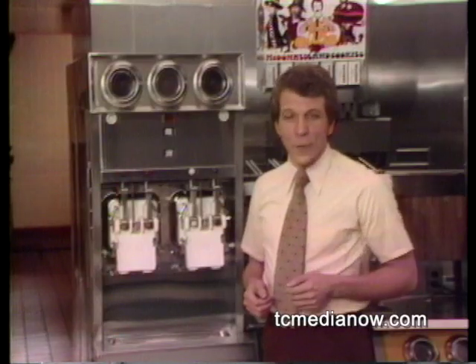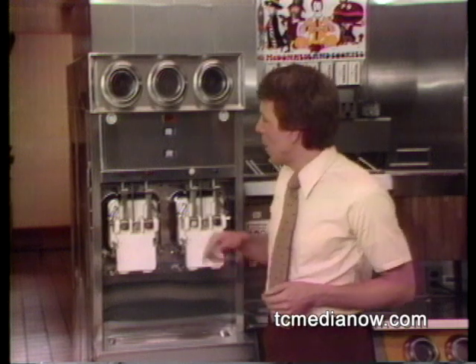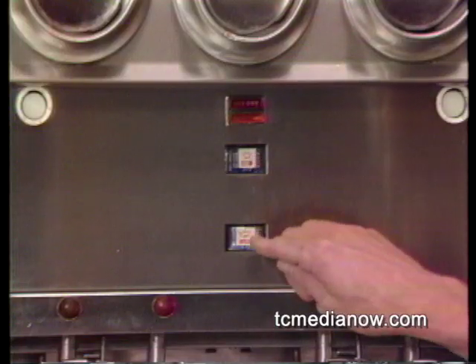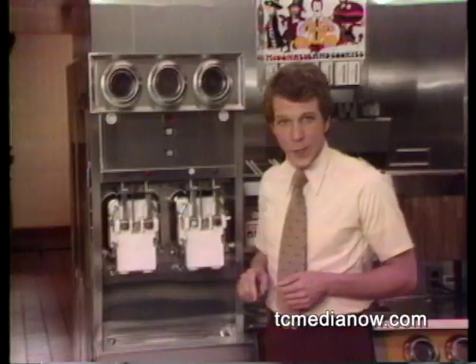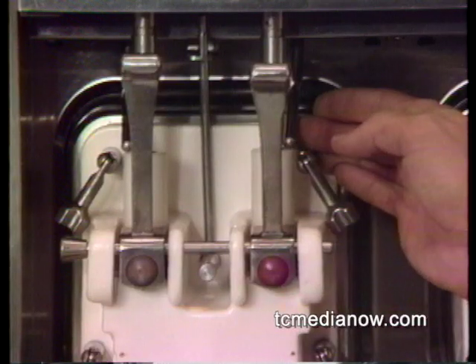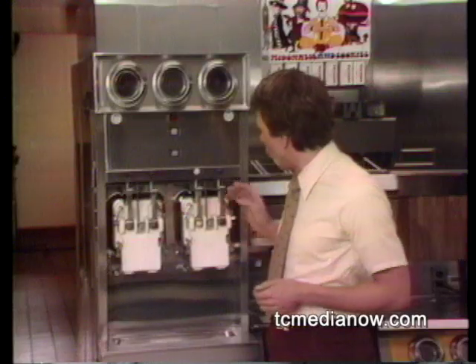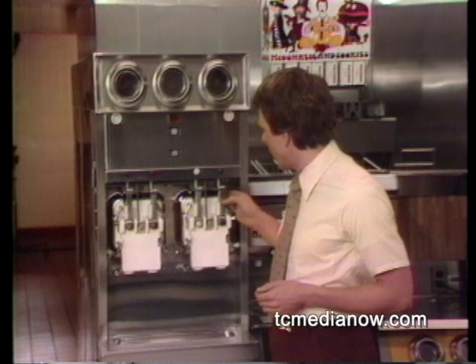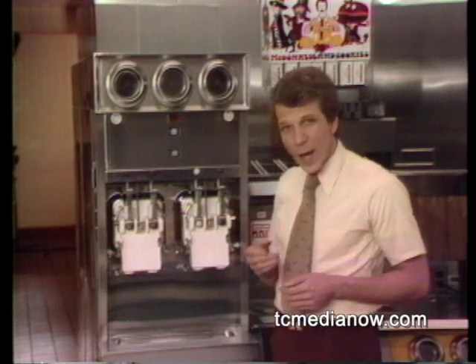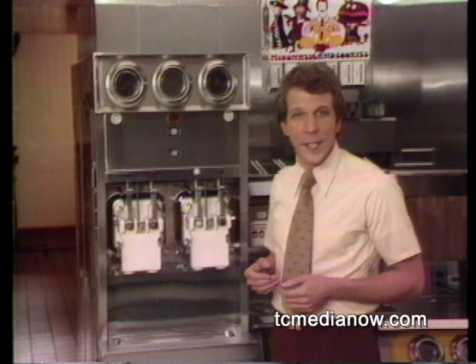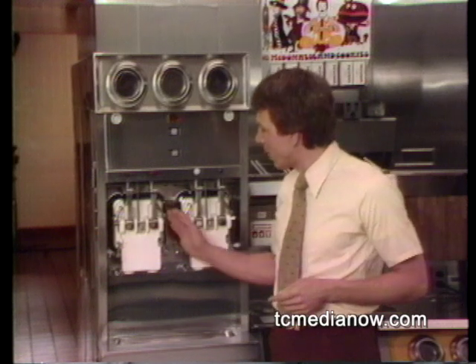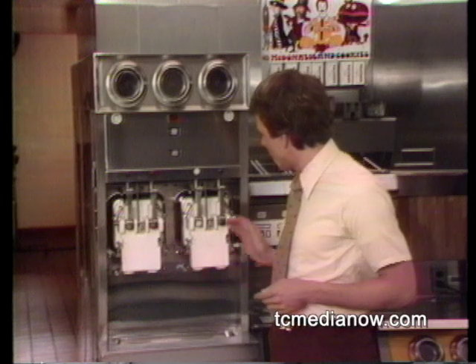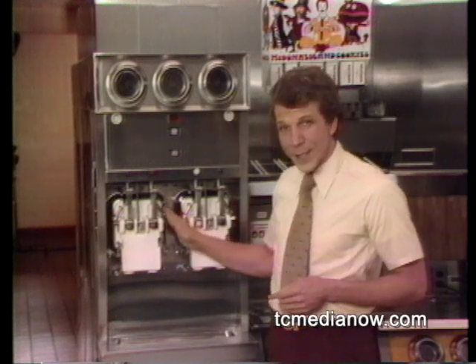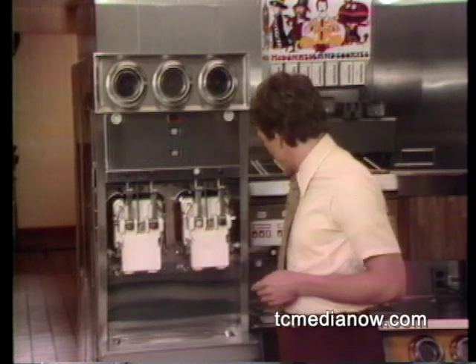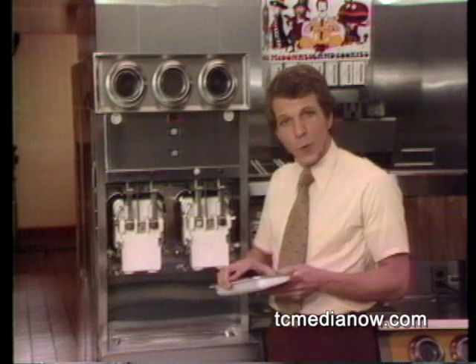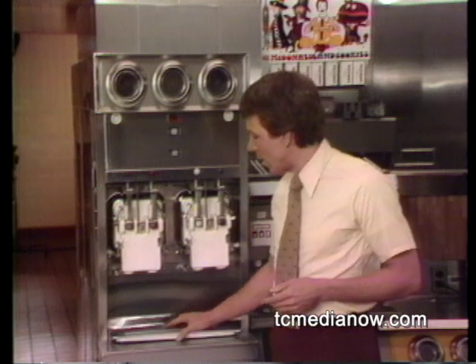Finally, after both freezing chambers have been primed, push the rocker switches on the panel above the freezing chamber to the auto position. You start the freezing cycle by slightly lifting one of the actuating arms from each freezing chamber. Allow the machine to complete the initial freezing cycle, and then check for leaks around the freezer door. Retighten the door fasteners if necessary. Put the drip tray into its spot under the draw valves.